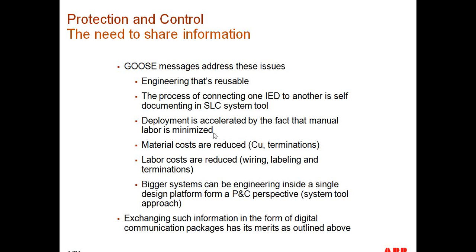Deployment is accelerated by the fact that manual labor is minimized. All of these connections do not require any terminal strips that need to be wired into or any terminations that need to be landed. It's doing the engineering in your system tool and downloading the files onto the relay. Material costs are reduced because copper terminations and terminal blocks are eliminated or reduced as part of a GOOSE-based protection and control scheme. And bigger systems can be engineered inside a single design platform from a protection and control perspective, thanks to the system tool and the ability to reuse blocks of engineering inside your system tool to replicate these types of connection.